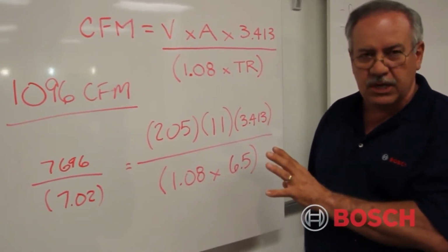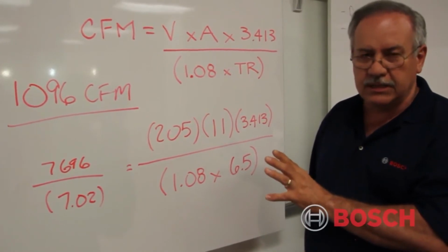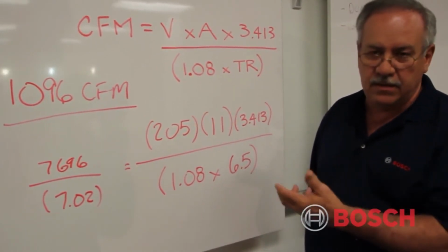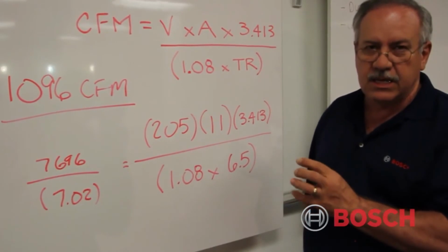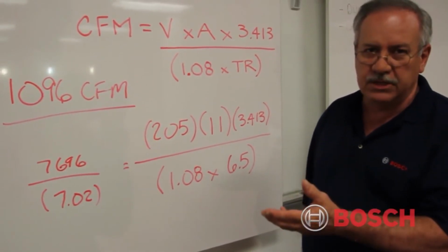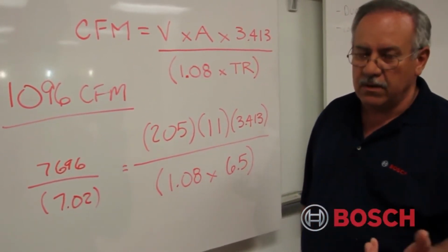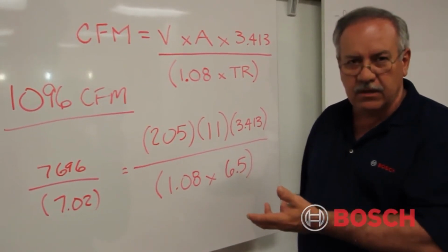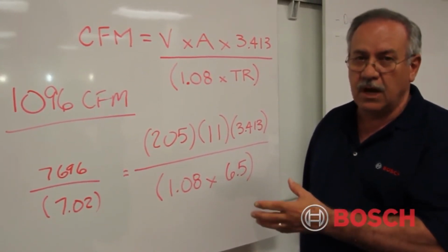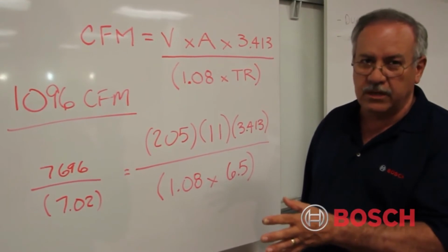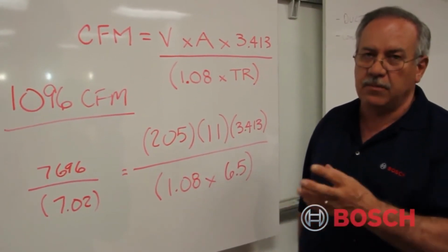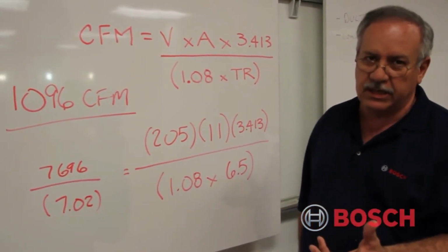So when all is said and done, in this particular case, I'm probably moving somewhere in the acceptable range. What that tells me in diagnostics, or in this setup, in the commissioning concept, is that I have the airflow crossing the coil in the heating mode, therefore I'll most likely have it in the cooling mode. So airflow is probably not an issue for this particular machine. The next step would be to check the waterside diagnostics.